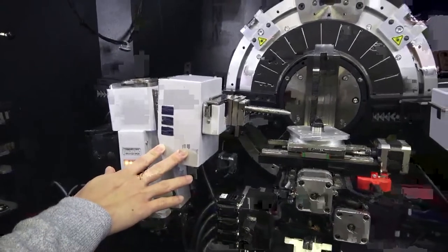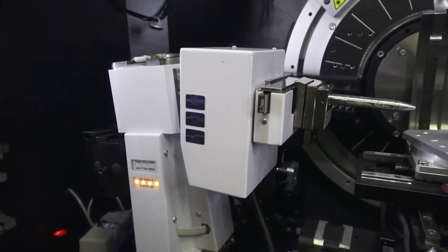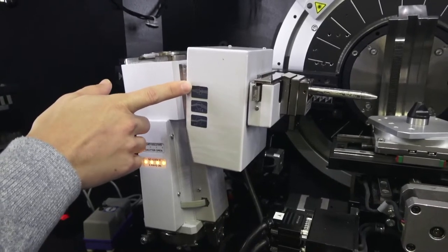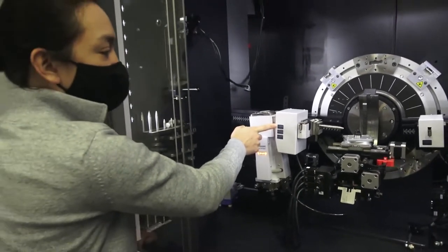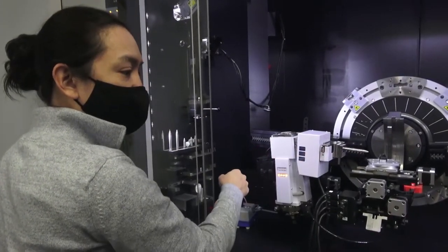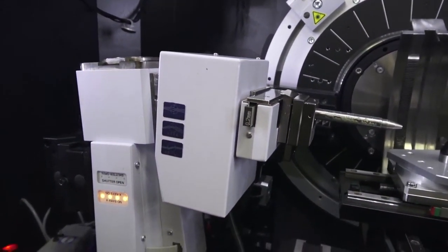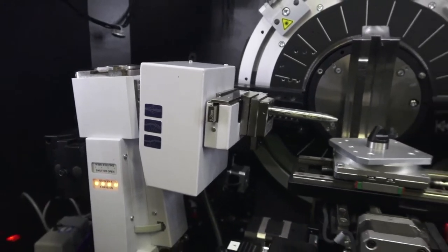This optic has three different components. The first is a diverging beam — used for traditional Bragg-Brentano powder diffraction applications. This gives you some Bremsstrahlung, copper K-alpha-1, K-alpha-2, and K-beta. To remove the K-beta, you'd need to couple this with a nickel filter on the primary or secondary slot, or with a detector like our LYNXEYE XE-T, which can remove that. A nickel filter takes out your K-beta, and will also cut some white radiation. The detectors generally have a discriminator good enough to get rid of a lot of that too.